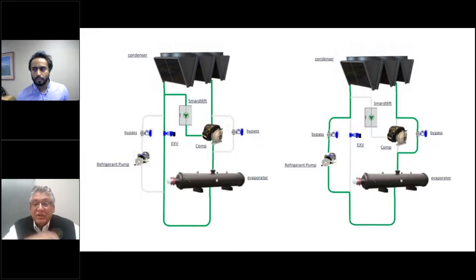I think you mentioned earlier that you use free cooling in an air-cooled machine by adding an additional module. Essentially you're running evaporator water, chill water, through a separate module within those air-cooled modules, and letting the condenser fan remove the heat for any times below 50 or 55 degrees. This is a little different technology. This actually uses free cooling within the air-cooled machine itself by adding a refrigerant pump. It's a little different application, but it does work. The efficiency and the capacities are comparable to free cooling with chill water through a heat exchanger. So, something unique to a smart air-cooled machine.